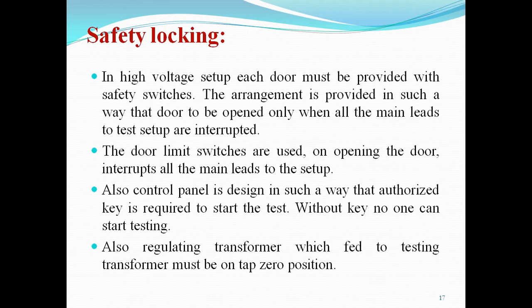This kind of contact is also given in the control panel, and therefore we need one authorized key. Once the authorized key is entered, then and only then can you start the experiment. Also, the regulating transformer which feeds the testing transformer must be at tap 0 position. This is also very important. So every time we have to put the transformer at 0 position. When all three interlocks are fulfilled, then and only then can we start the experiment, which we will see in the laboratory experiment.